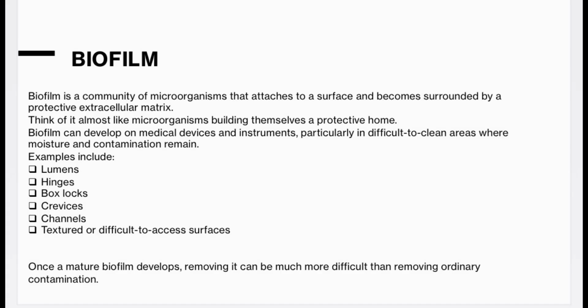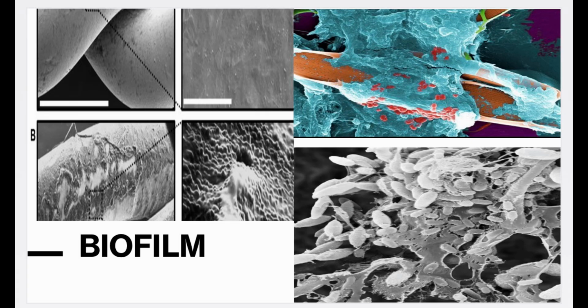Biofilm normally develops on instruments that have difficult internal areas to clean, because over time, they develop a protective matrix, which makes it more difficult to remove. That is why what happens before the instrument even reaches the sterilizer is very important: it must be properly cleaned, following the manufacturer's IFUs.